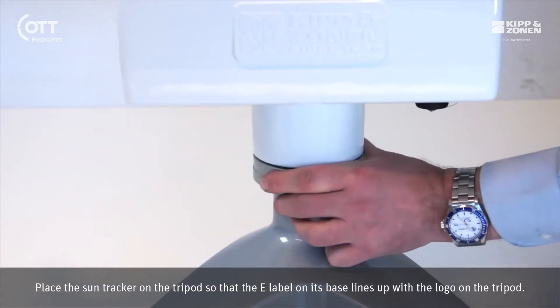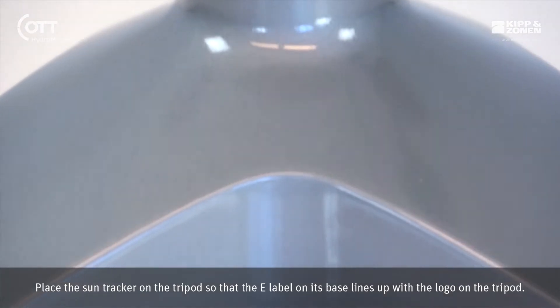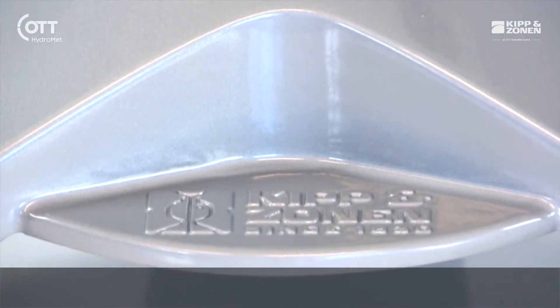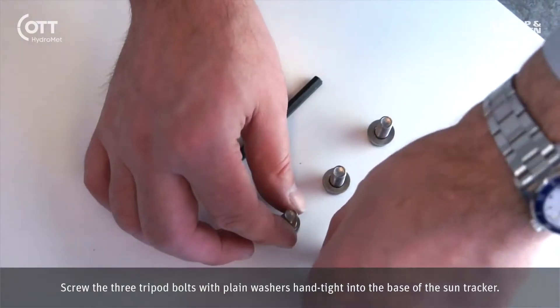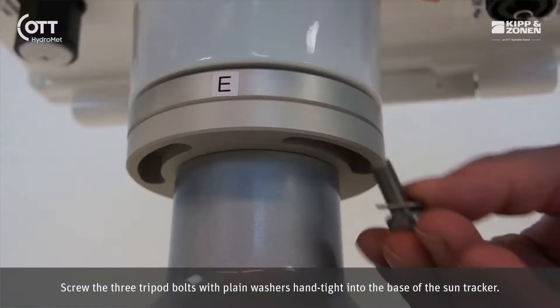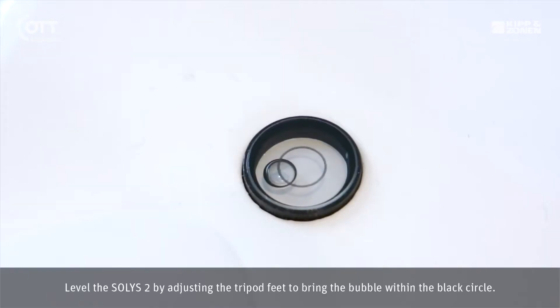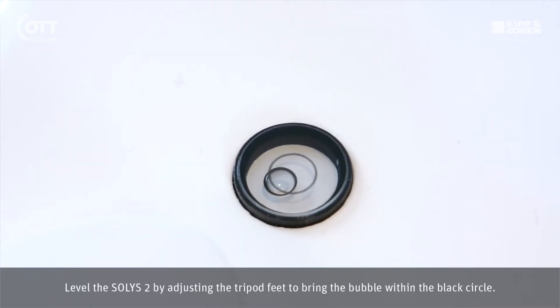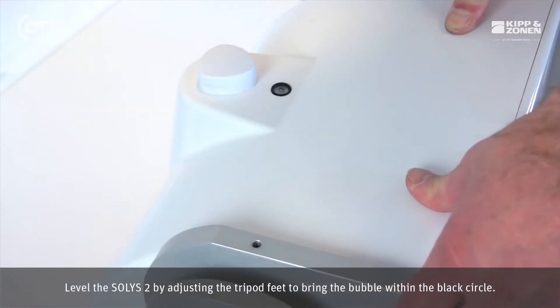Place the SunTracker on the tripod so that the e-label on its base lines up with the logo on the tripod. Screw the three tripod bolts with plain washers hand tight into the base of the SunTracker. Level the SOLYS 2 by adjusting the tripod feet to bring the bubble within the black circle.